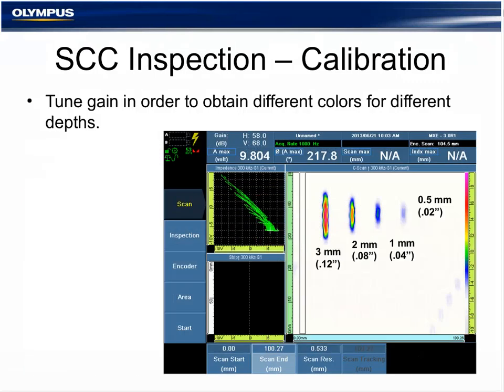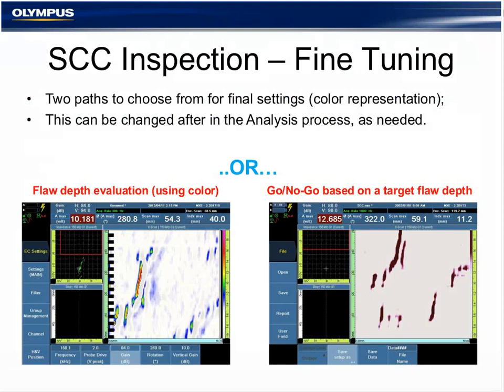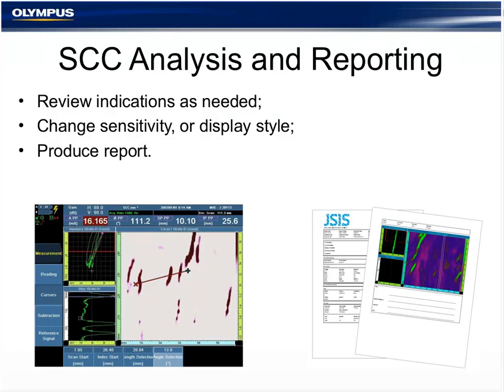So, the entire goal of the calibration step with ECA is to tune the parameters correctly, of course, and to obtain different colors for the different depths of the defect. In that example, I have 4 flaws, from a short to a long one, and the shorter is less deep anyway. So the display was tuned to have 4 different colors. It's possible to select from 2 methods. Either you display the colors for the depth, or it can be configured as a go, no-go based on a specific flaw that is agreed with the end customer to be detected, and a smaller flaw not to be detected, for instance. We're going to see both methods in the demo. Then the analysis and reporting, using the cursor, changing sensitivity or display style, and producing the report as the last step, and we are also going to see that in a minute following the calibration steps.